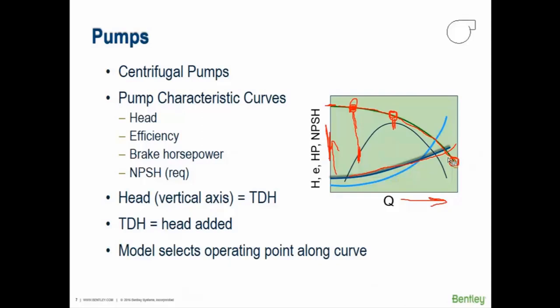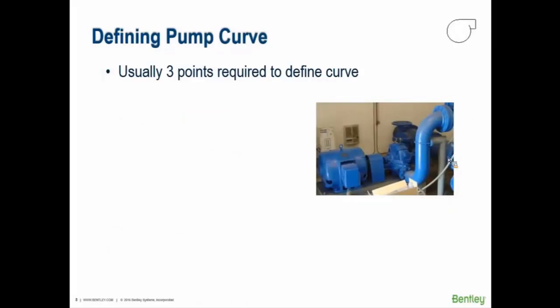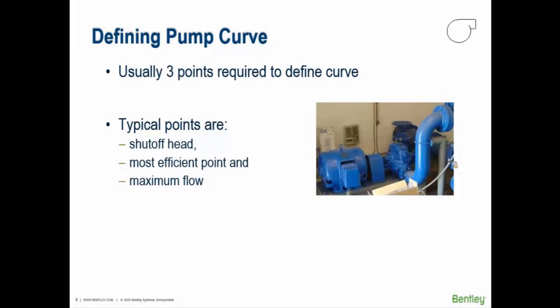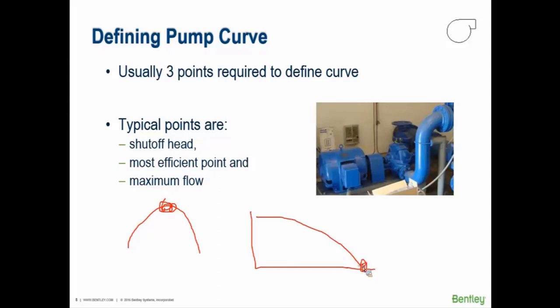In WaterCAD and WaterGEMS you typically use three points to define the pump curve: the shutoff head (where the pump shuts off when pressure reaches a high point), the most efficient point (the peak of the bell curve), and the maximum flow or runout point. Maximum flow doesn't necessarily mean where the curve hits the axis at near-zero head — pumps will trip off before that. Refer to the pump manufacturer catalog for the actual maximum flow.